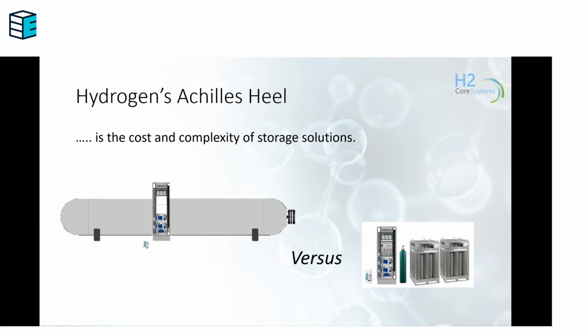While the Enapter AEM is nice in that it produces hydrogen at 35 bar pressure, and that can be fine for many applications, we do provide low pressure 35 bar storage solutions in single vessels, which can be as large as 115 cubic meters, holding 325 kilograms of hydrogen. But being practical, a vessel of that size would typically be 40 meters long and weigh about 39,000 kilos.